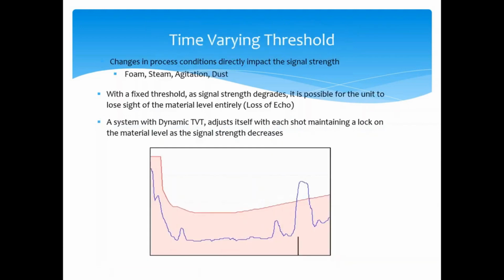Sure. So the question is, if the signal never crosses the red line, that threshold line, will this report a loss of signal? Yes, if your signal never gets above that red threshold, you will be in an echo loss mode. And what happens to your output? You can set it up for one of three scenarios. You can set it up to fail high, which means above 20 milliamps, so typically 22 milliamps. You can fail low, below 4 milliamps, typically 3.6 or 3.8 milliamps, or you can hold your last known good value. And that's all programmable through the instrument.